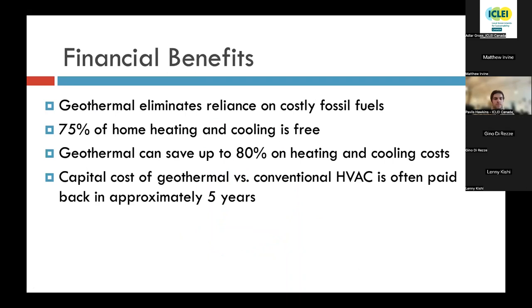So geothermal systems offer financial benefits because they eliminate the reliance on costly fossil fuels and they provide 75% of home heating and cooling for free. Geothermal systems can save up to 80% on heating and cooling costs, depending on what your fuel type is and what the cost per liter is at any given time, but it eliminates that volatility. And then the capital cost of a geothermal system versus a conventional HVAC system is often paid back in approximately 5 years, sometimes more quickly, sometimes a little less quickly. But when you're talking about eliminating a $4,000 or $5,000 or $6,000 oil or propane bill, the several thousand dollars more that you're paying for a geothermal system over 20, 25 years is a significant savings over the life cycle of that equipment.